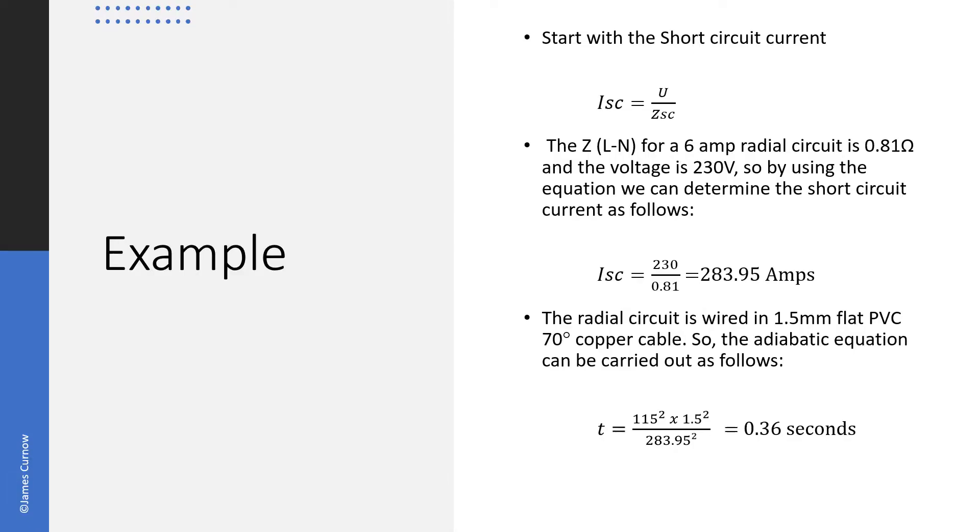Here we have an example and what I always do is start with the short circuit current which can be calculated by dividing the voltage by the Zsc. If the ZL to N for a 6 amp radial circuit is 0.81 ohms and the voltage is 230 volts, we can determine the short circuit current: 230 volts divided by 0.81 which gives us 283.95 amps.